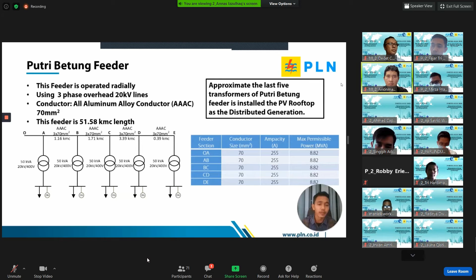Approximately the last 5 transformers of the Putri Betung feeder have PV rooftop installed as distributed generation. The last 5 transformers have the same capacity, which is 50 kilovolt ampere. We can see in the table the ampacity of the conductor is about 255 ampere, and the max permissible power in megavolt ampere is about 8.82.